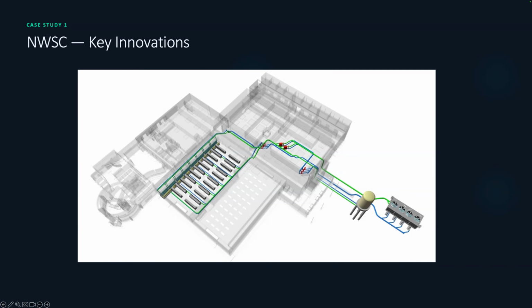We also played some games with the geometry, so that the tank is relatively tall and skinny, which gave us a lot more head pressure, which meant that if a pump would fail, gravity would still drive cold water to where we wanted it to go.